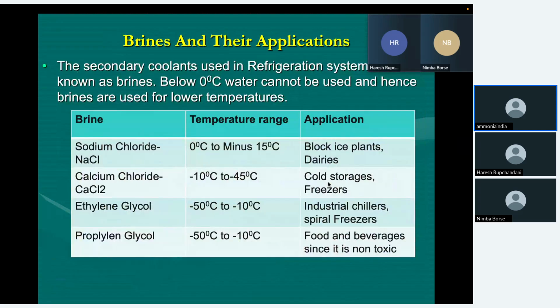The next point: we discuss brines and their applications. Let us look at what brines are. Brines are secondary coolants used in refrigeration systems for temperatures below 0 degrees. Water cannot be used below 0 degrees because it will form ice. So brines are used for low temperature applications. What are the common brines which are normally used? For a commercial plant, a lot of people use sodium chloride brine.